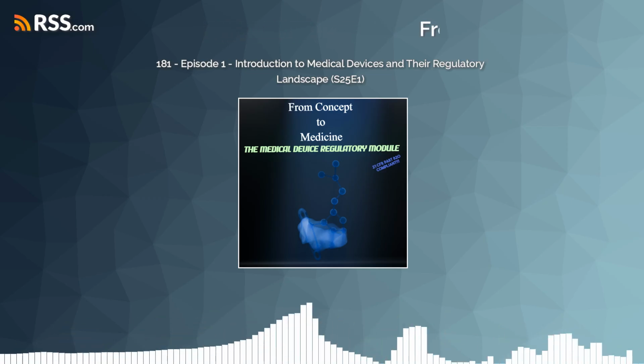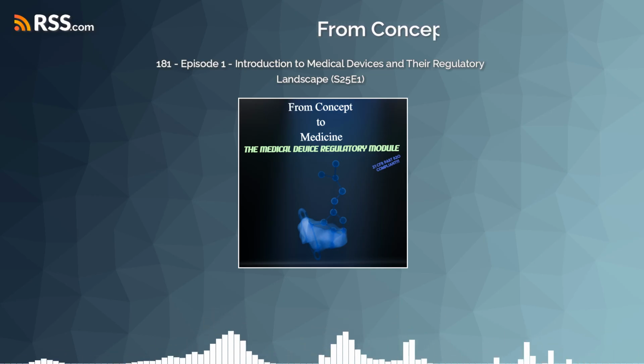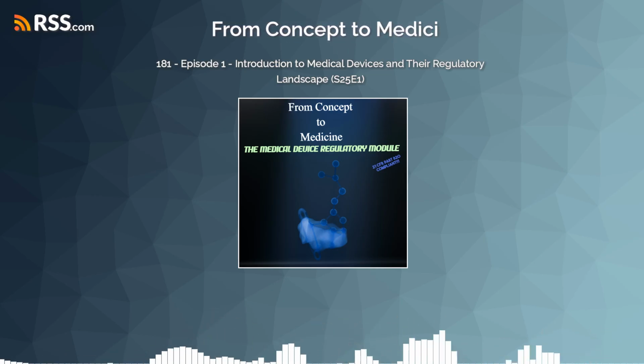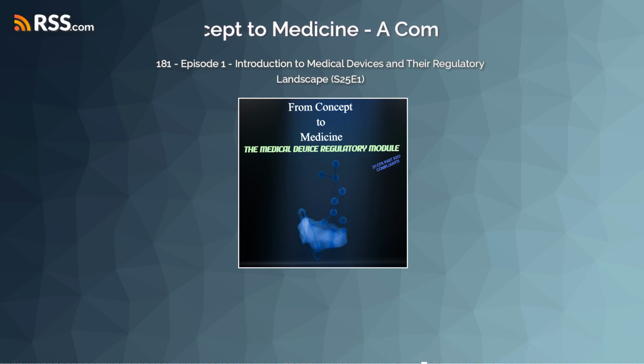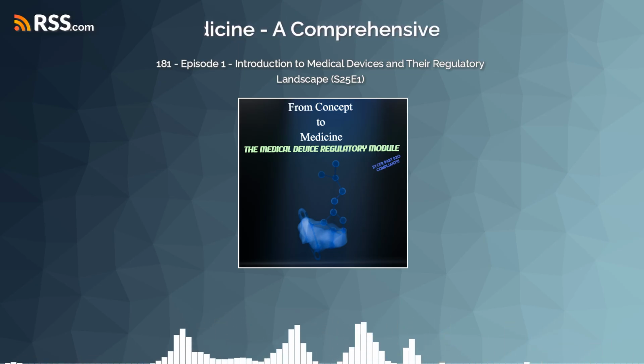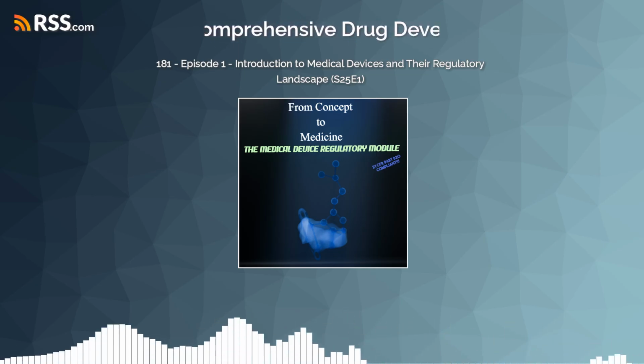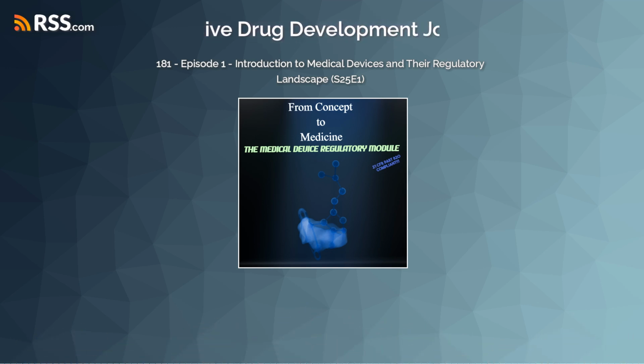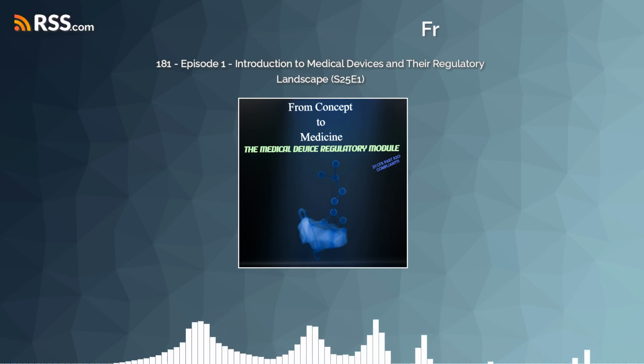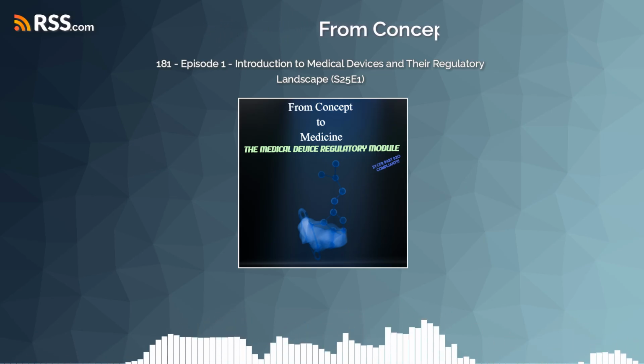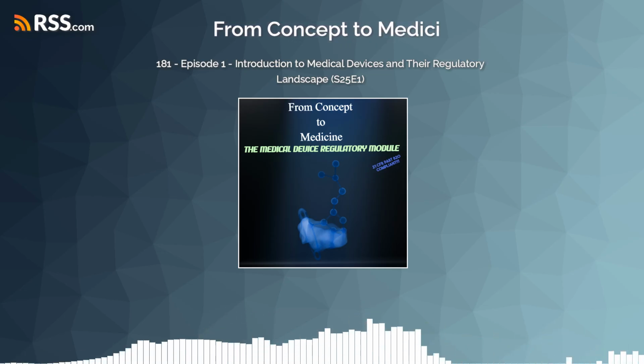IDEs. Okay. An approved IDE allows a device that would normally require pre-market approval or clearance, like a Class 3 device, or sometimes a Class 2 needing clinical data, to be shipped lawfully for investigational purposes. So it lets you test it in people. Primarily, yes. It allows the sponsor to conduct clinical investigations on human subjects to gather the necessary safety and effectiveness data needed for that eventual PMA, or sometimes even a 510(k) or de novo.